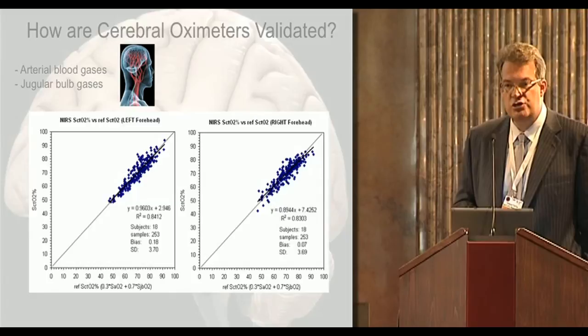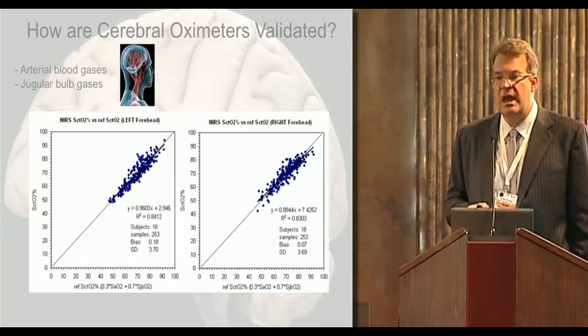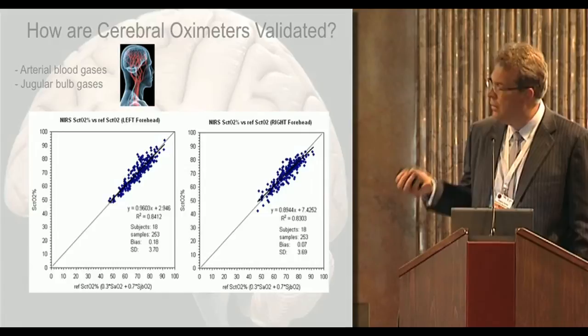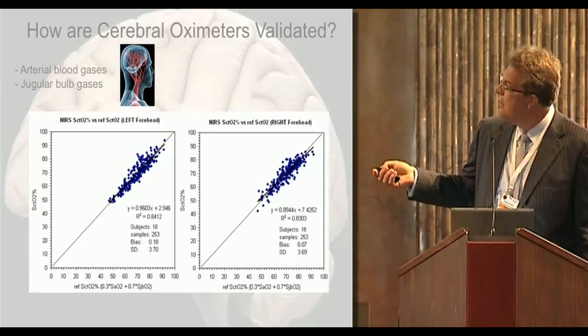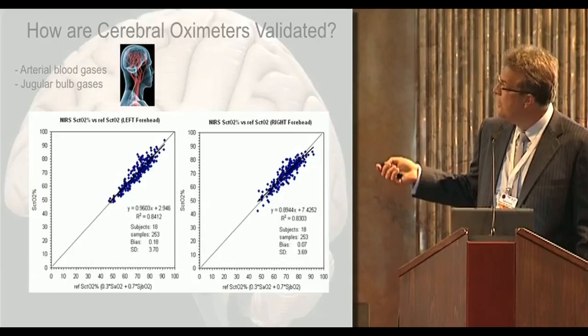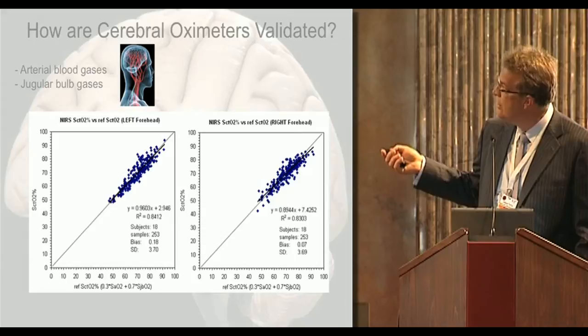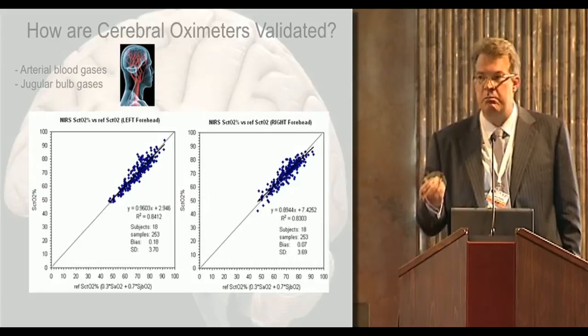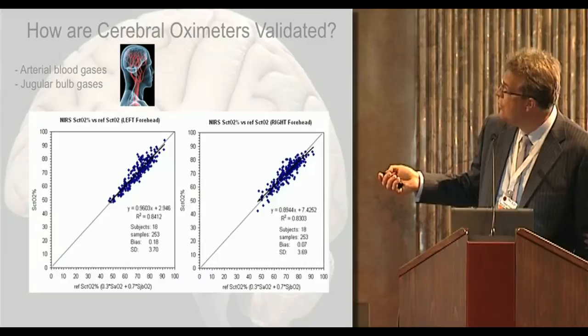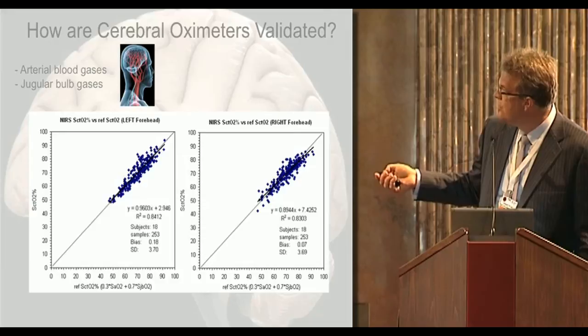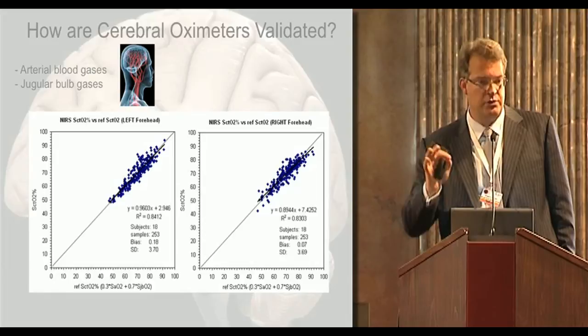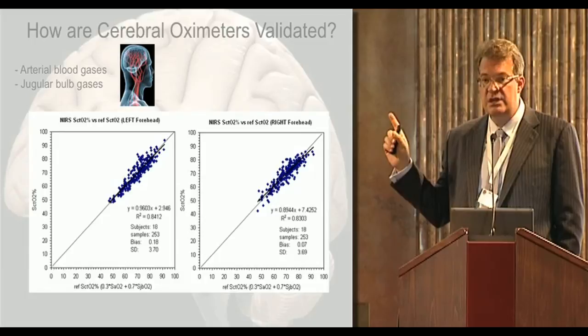Here you can see the reference ScO2 — measured invasively and calculated with a co-oximeter — compared to the ScO2 actually displayed by the machine. This shows how precise the oximeter is. This is the Foresight, and you can see how all the individual measurements stick to the reference line. It has a standard deviation of about 3.7%. Modern pulse oximeters are about 2–3% on their standard deviation, so the cerebral oximeter is just a little bit higher. The Foresight is a very precise device.